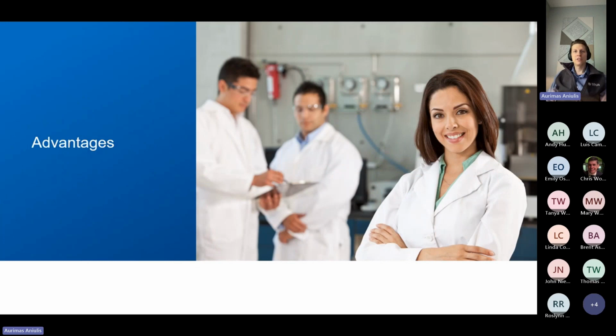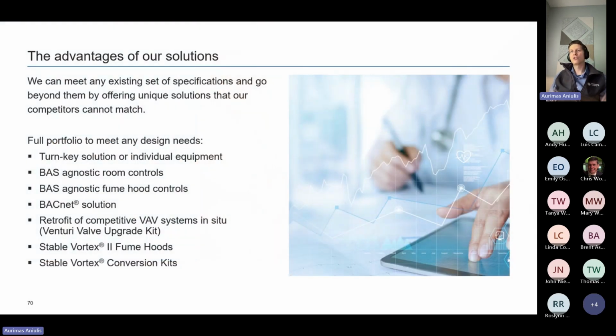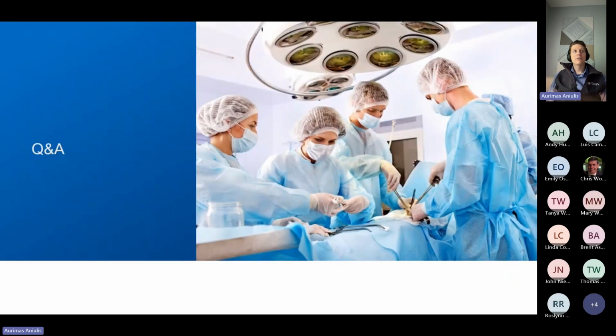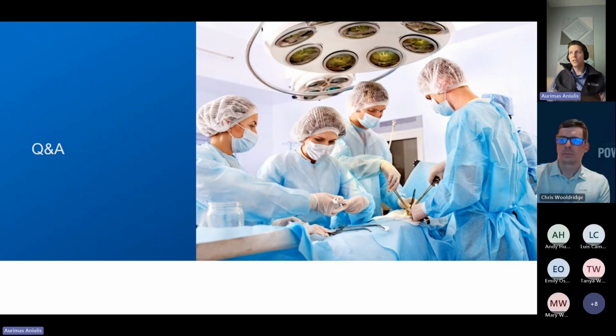So finally, to summarize in the last couple of notes, the advantage of our solution is that we can provide a turnkey solution or individual equipment for whatever little piece you need. You can piecemeal it together or you can get one system that ties together. We are BAS agnostic. What that means is we talk BACnet MSTP. If there's an existing controls platform you want to use, our equipment seamlessly ties into that. BAS agnostic fume hood controls, that's important. Retrofit kits are available for both Venturis and fume hoods, and again, a high efficiency fume hood to help tie the lab solution together. And with that, I'm going to pause and take any questions.